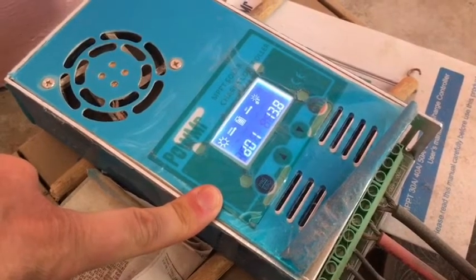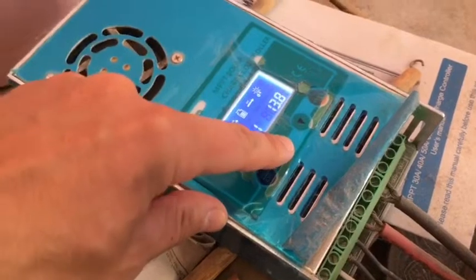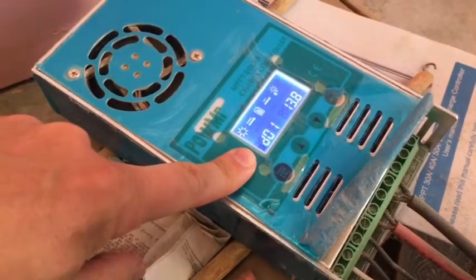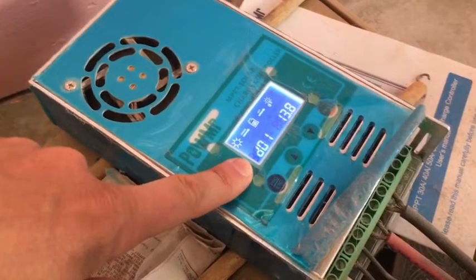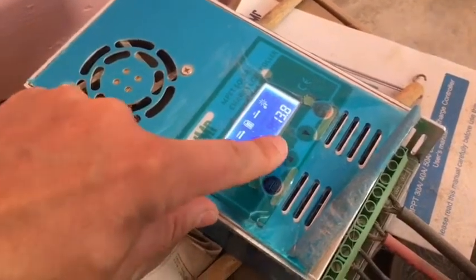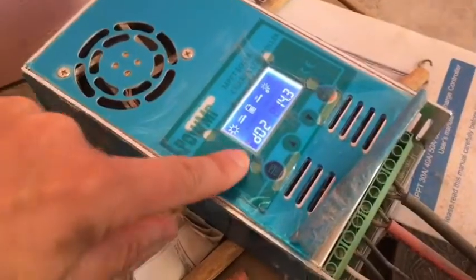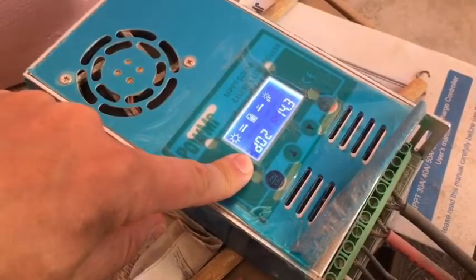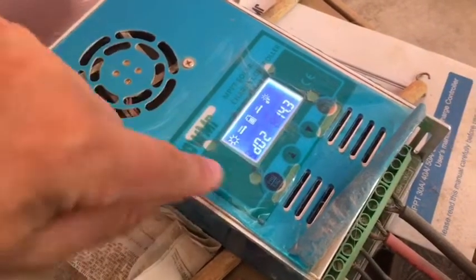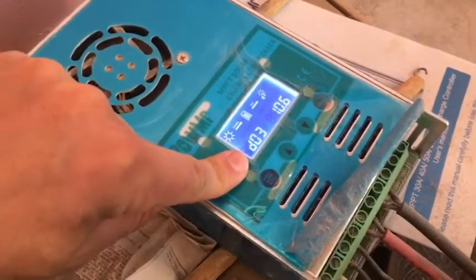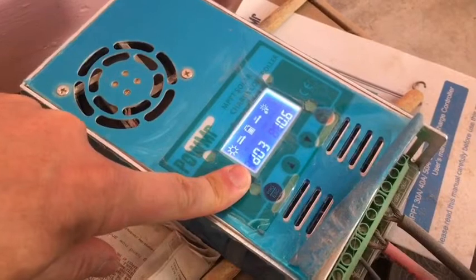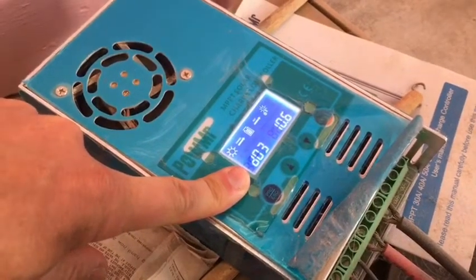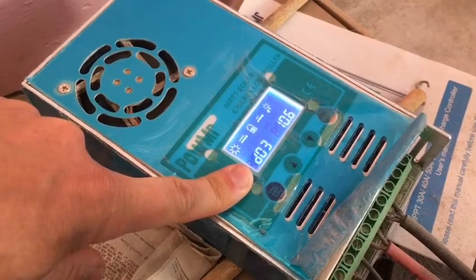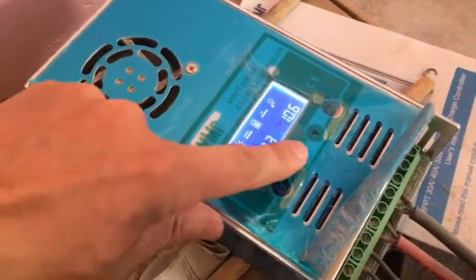So what does this translate to? That's 26 plus 1.6, so I guess that's the equalized charge. There's no real equalization charge for a lithium battery bank, so I'm not really sure what this is. I just set it at what I thought might be a safe setting, 27.6. D2 is the maximum it will charge to, which I've got set at essentially 28.6 - that's 14.3 doubled. And this is where it cuts off at the low end, which I've got set to 21.2, I guess. I don't know what that means exactly.